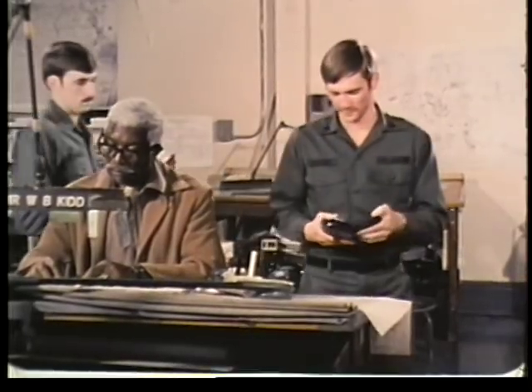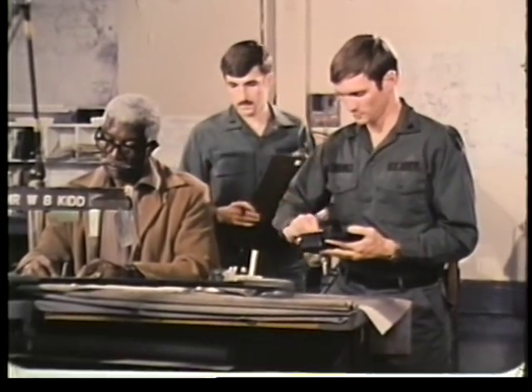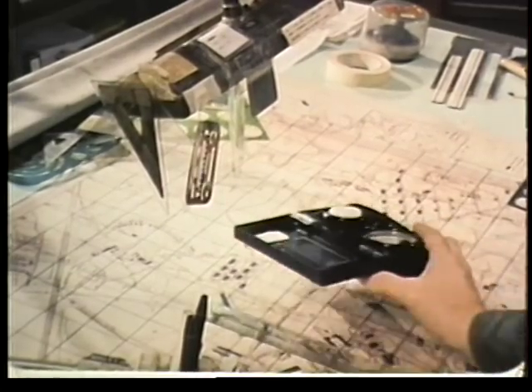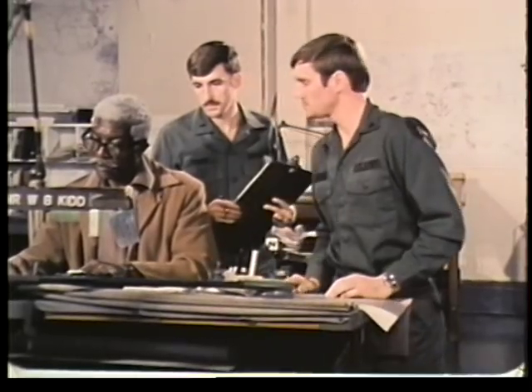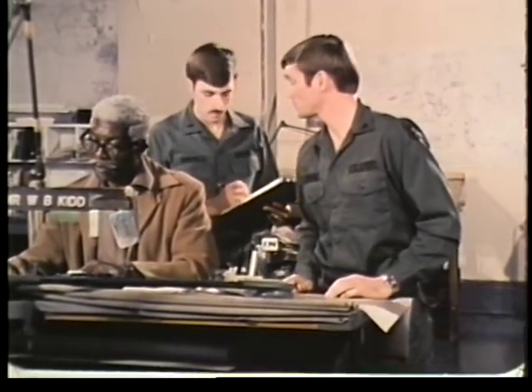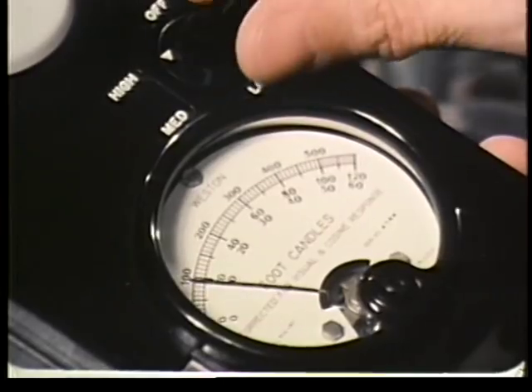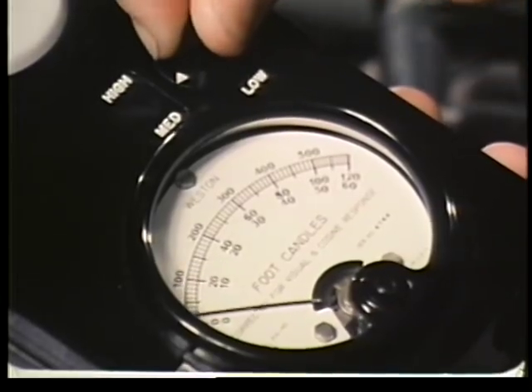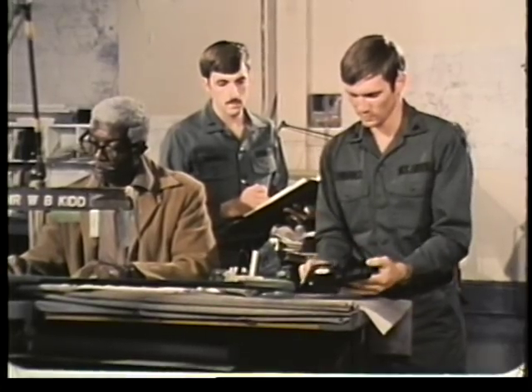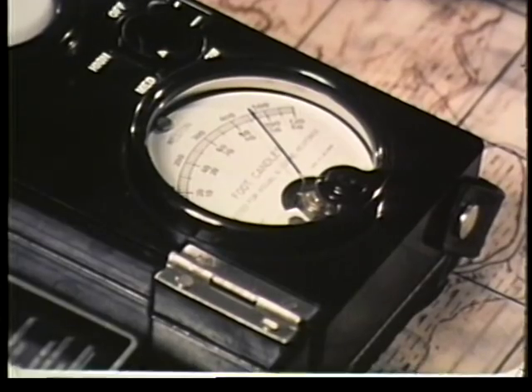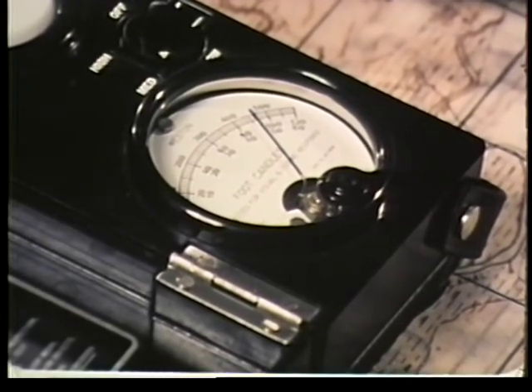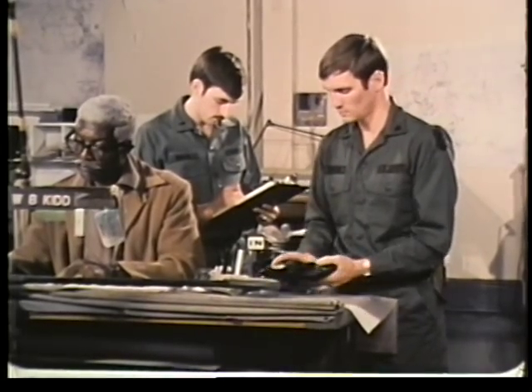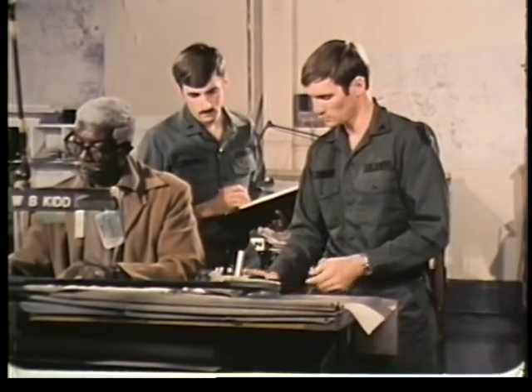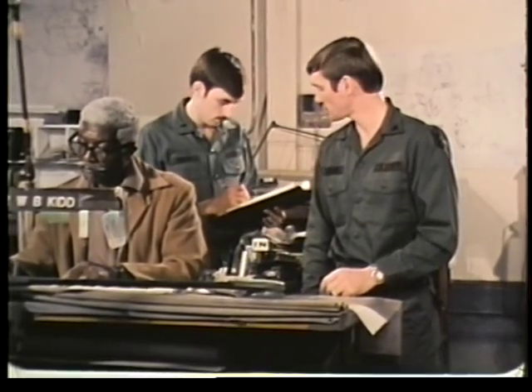The procedure for measuring the light levels is straightforward. Place the light meter on the work table or desk. Note and record the reading. When moving the meter from one area to another, it may be necessary to shift to a different sensitivity range. The reading is given in foot candles. Before you're finished, you'll take similar readings at each work area in the room.